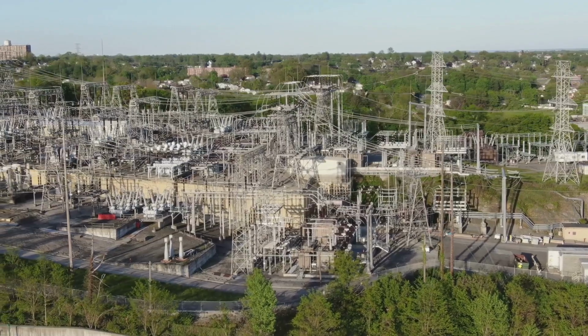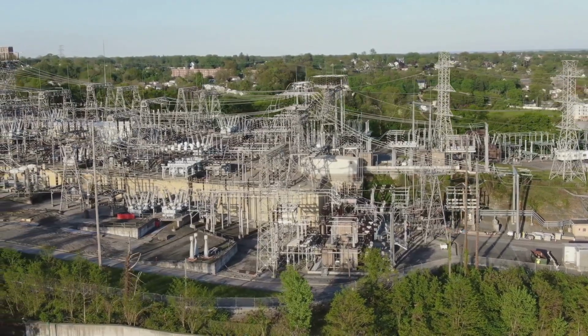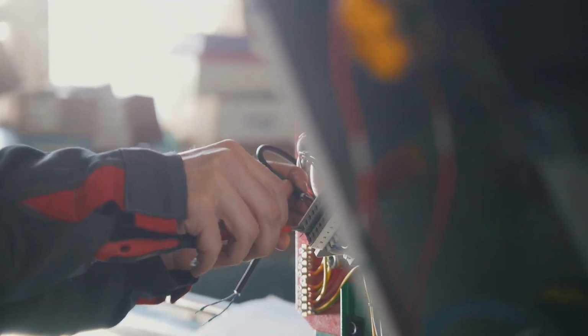A DER that successfully rides through a fault must still maintain AC waveform integrity. DC suppression is part of ensuring that the DER contributes to grid recovery, not degradation. Clause 7.2, Voltage fluctuations and flicker control.